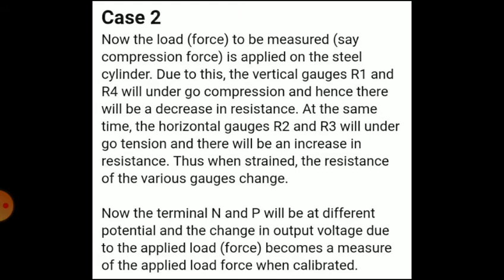Case 2: now the load, that is, the force to be measured, say a compression force, is applied on the steel cylinder. Due to this, the vertical gauges R1 and R4 will undergo compression and hence there will be a decrease in resistance due to the compressive force. At the same time, the horizontal gauges R2 and R3 will undergo tension and there will be an increase in resistance. Thus, when strained, the resistance of the various gauges changes. Now the terminals N and P will be at different potential, and the change in output voltage due to the applied load becomes a measure of the applied force when calibrated.